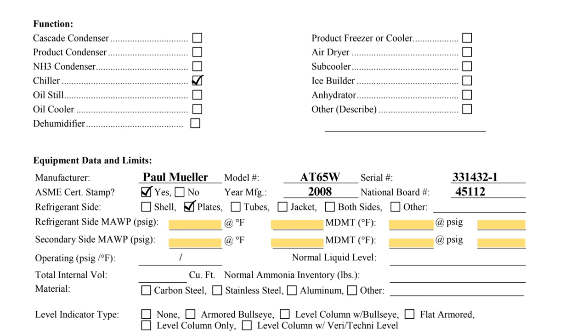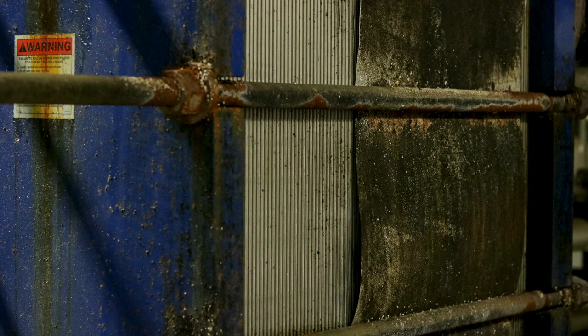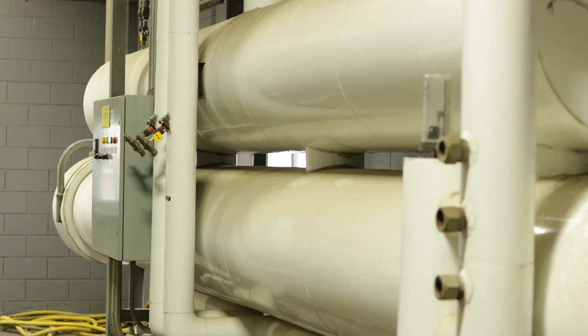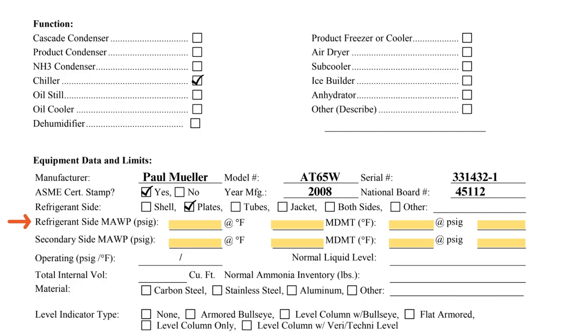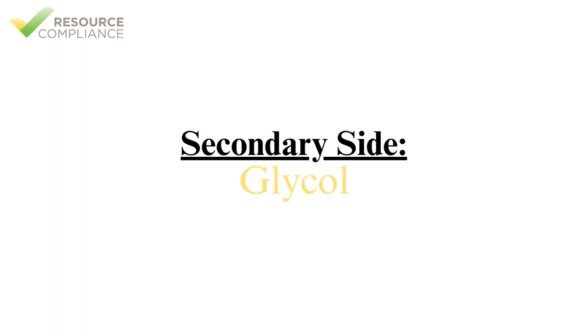The questions referring to refrigerant side, refrigerant side maximum allowable working pressure (MAWP), and secondary side MAWP are unique to the heat exchanger checklist. This is because the purpose of the heat exchanger is to transfer heat from one substance to another without direct contact of the substances. Therefore, one side of the heat exchanger pertains to the primary refrigerant, and the other side refers to the secondary substance being cooled. In this example, the refrigerant side will be ammonia, and the secondary side will be a glycol solution.